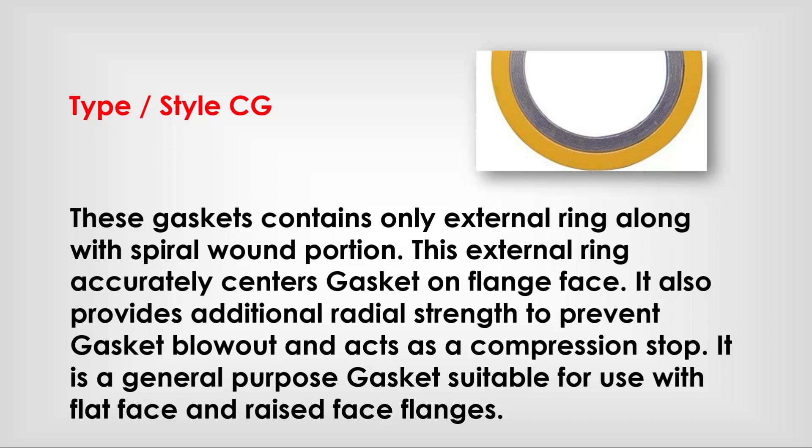Type style CG: these gaskets contain only an external ring along with the spiral portion. This external ring accurately centers the gasket on the raised face and provides additional radial strength to prevent gasket blowout, acting as a compression stop. It is a general-purpose gasket suitable for use with flat face and raised face flanges.